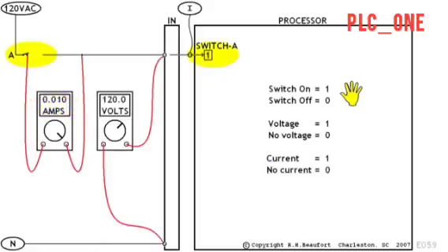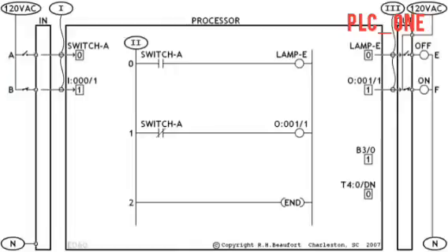Here we've fixed the broken wire, and now the on position of the switch does give us a 1 in the bit. Different input modules have different specifications for on and for off signals. The meter readings we're showing here are pretty typical for the type of hardware we're using for our video lessons. And here's where we stand so far. The sketch is starting to look a little crowded, but since we're covering everything step by step, all of the pieces of the puzzle should be falling into place for you. If not, you can always just watch the videos again for a quick review.